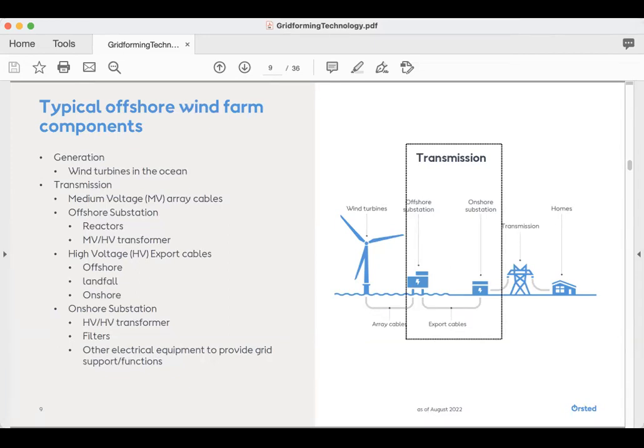From there you have the export cable. The export cable voltage can be anywhere, generally over 100 kV. Most of our designs use up to 275 kV HVAC cables.